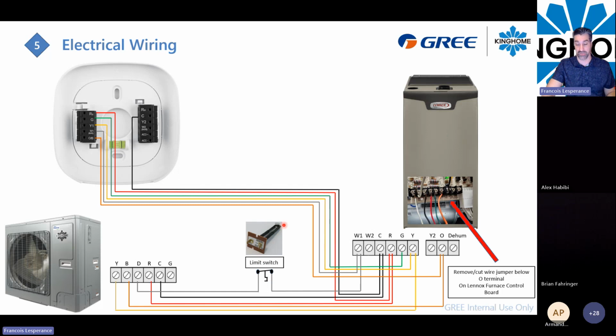And when you reach 100 Fahrenheit, this switch here will open, so that will cut the power to W1. And so you will continue the defrost cycle of the outdoor unit, but you will not overheat the refrigerant. You will not bring the refrigerant to reach that 667 psi. Is that good? No more question on that?